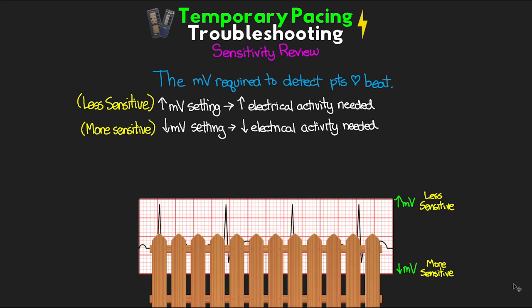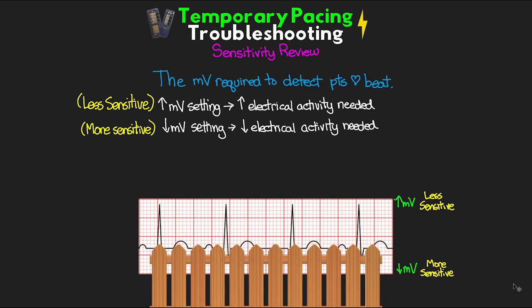If we go too far and make it too sensitive, we'll begin to see T-waves and pick those up as additional beats of the patient's intrinsic rhythm. So remember: the higher the fence and the higher our millivolt setting, the less sensitive we are to the underlying rhythm; the lower the fence and the lower the millivolt setting, the more sensitive we are. It's really important to understand this setting in order to do the troubleshooting we need to do.